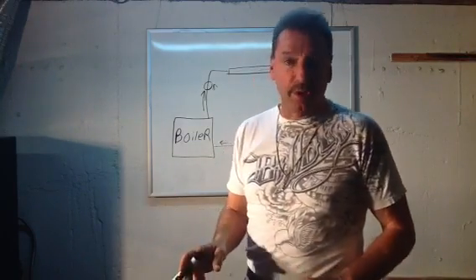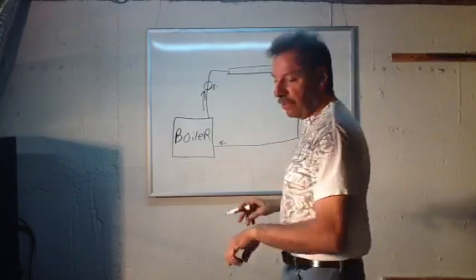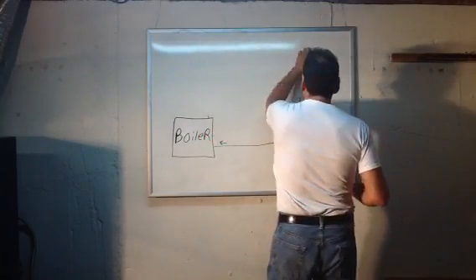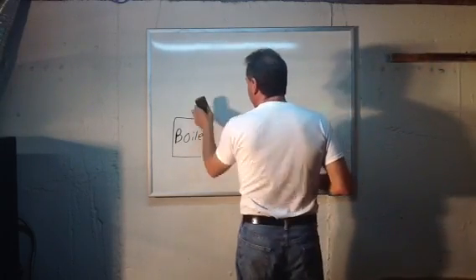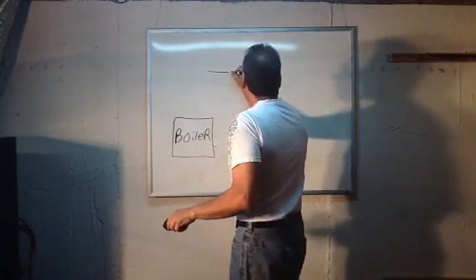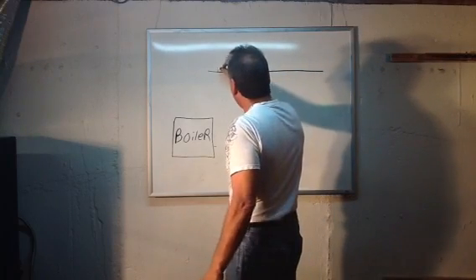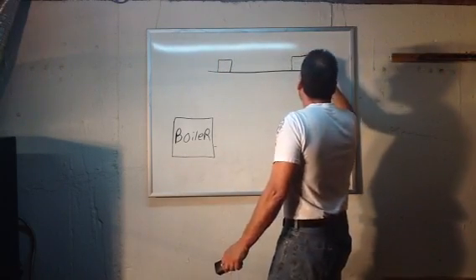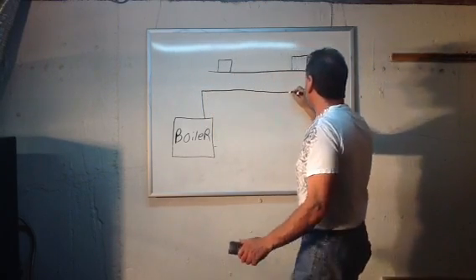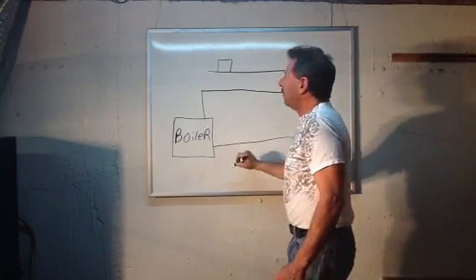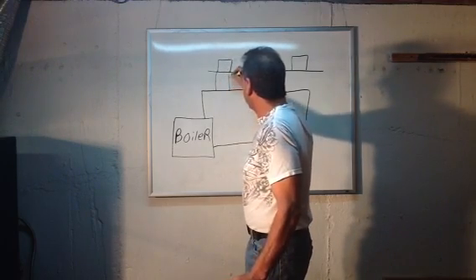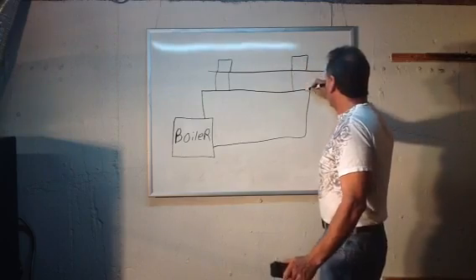A lot of times people experience some baseboards heat and some don't. More times than not, this is what happened, especially in old houses that were converted years ago. They wouldn't have baseboard, they'd have these little convectors on the floor. What the plumber did was he ran a large pipe along the basement ceiling and back to the boiler, but the convectors were tied in with half-inch monoflow tees.